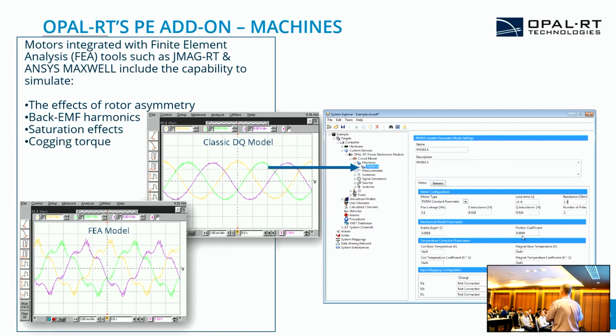You need to have finite element analysis models. Those models actually consider the stator of the motor and the rotor turning inside. What happens is that when the notch between the stator and the rotor is in front of it, your impedance value changes because the rotor moves to the next notch. So between each notch, the impedance changes. It's a 3D matrix - your impedance will change based on the position of the rotor from 0 to 360 degrees, and repeat. The impedance also changes with the power - if you're working at 10 ampere or 100 ampere, it's not the same impedance. This means that in steady state, a real FEA motor has some harmonics on it.